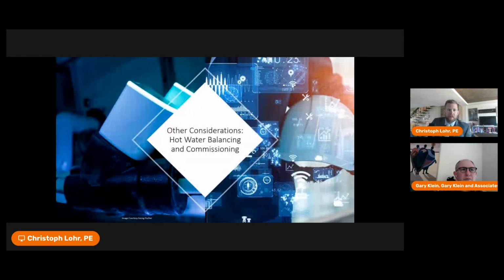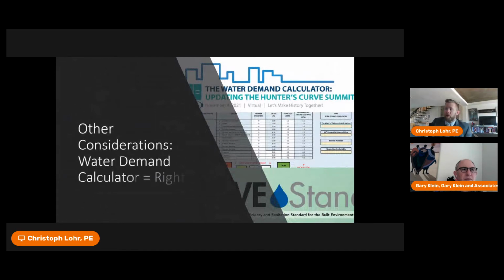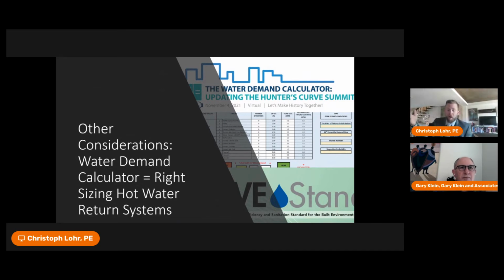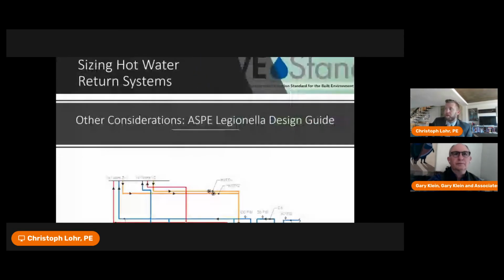Again, I mentioned the need for hot water balancing and commissioning. That is a requirement that is going to be needed for the facility. We also have right sizing hot water return systems. And in order to right size hot water return systems, utilizing the right supply pipe sizing can have a drastic impact on what your assumed BTU losses are through the hot water supply and return systems, which can shrink your hot water return pipes and pumps as well.